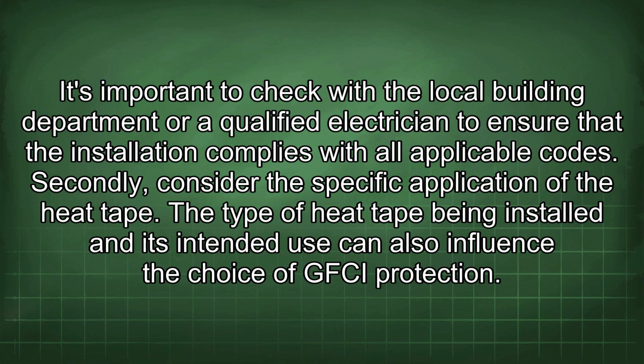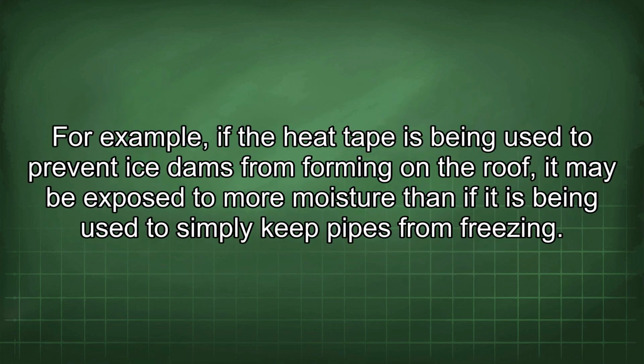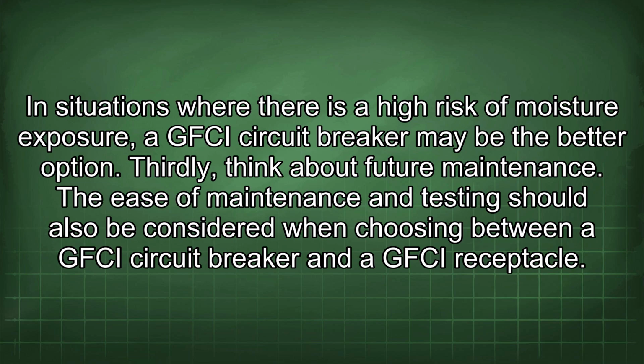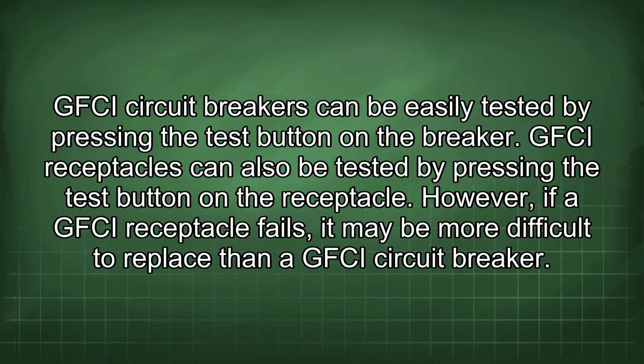The type of heat tape being installed and its intended use can also influence the choice of GFCI protection. For example, if the heat tape is being used to prevent ice dams from forming on the roof, it may be exposed to more moisture than if it is being used to simply keep pipes from freezing. In situations where there is a high risk of moisture exposure, a GFCI circuit breaker may be the better option. Thirdly, think about future maintenance. The ease of maintenance and testing should also be considered when choosing between a GFCI circuit breaker and a GFCI receptacle. GFCI circuit breakers can be easily tested by pressing the test button on the breaker.